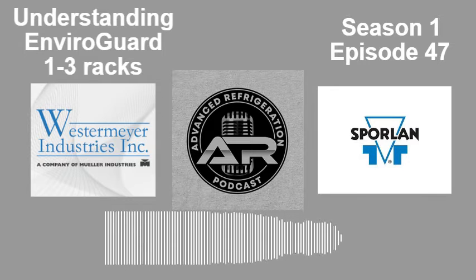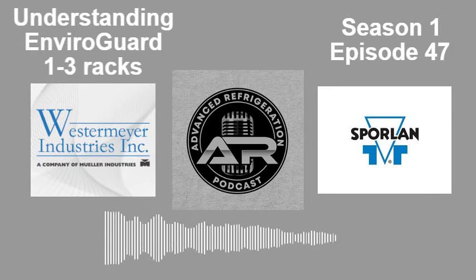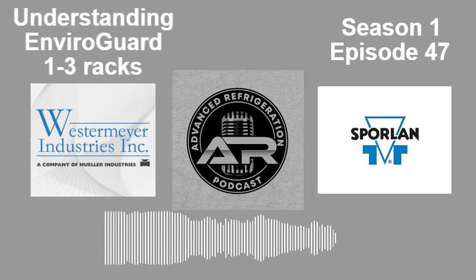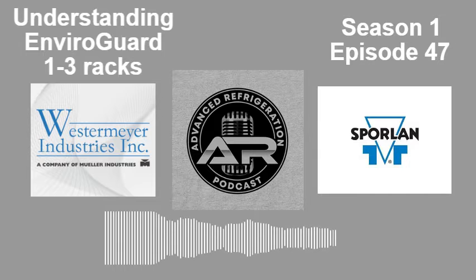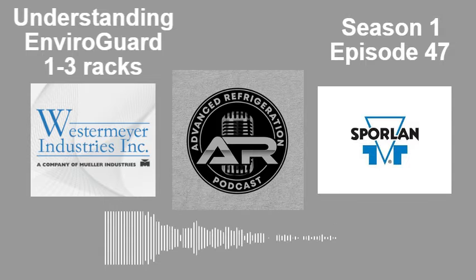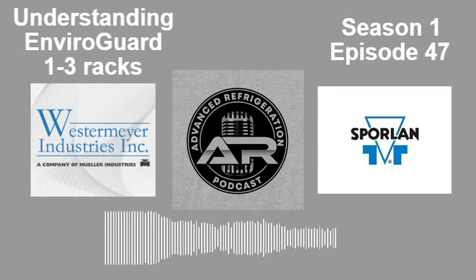What's their stance on, because I'm asking because I don't know, mounting the transducer up by the condenser so you don't have to have an effect for that static pressure? So obviously Tyler didn't do that, but a lot of the SR racks do, like the Costco style. They started doing that a lot. I mean, to be honest, I like it on an EnviroGuard. I would think it would be better, but I think that the difference would be minimal.